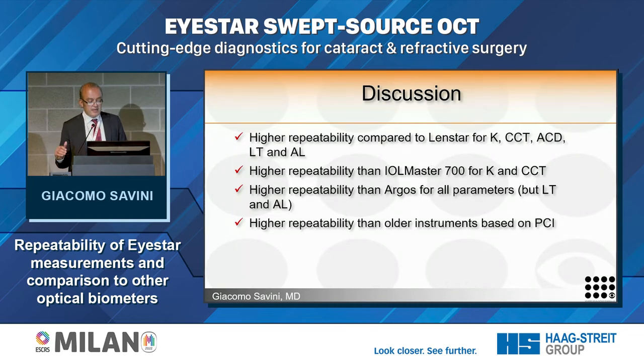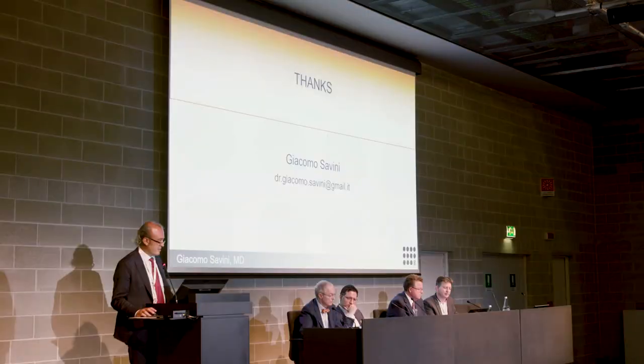The Eyestar had higher repeatability compared to LENSTAR for K, CCT, ACD, lens thickness, and axial length. It had higher repeatability than the IOL Master 700 for K and CCT, higher repeatability than Argos for all parameters except lens thickness and axial length, and higher repeatability than older instruments based on partial coherence interferometry. That's all. Thank you.